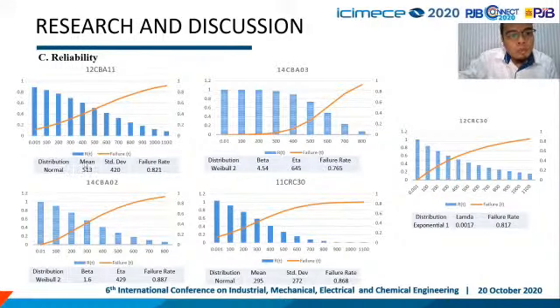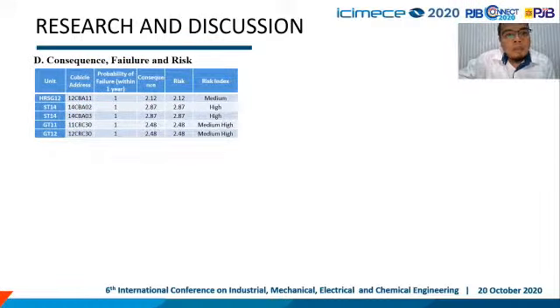is normal, with mean 513, standard deviation 420, failure rate 0.8. This whole data we carry to the next step, the consequence of failure and risk. This is the result of the probability of failure within 1 year. Every cubicle has the potential to fail within 1 year. Based on the risk index, those at a high level are 14 CBA 02 and 14 CBA 03. These are the DCS that control the steam turbine.